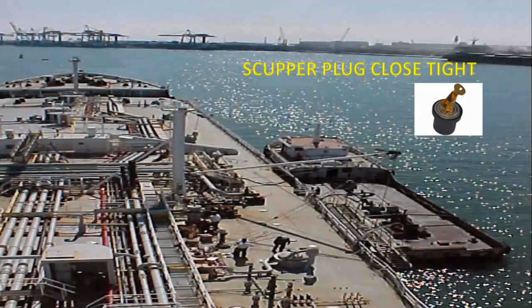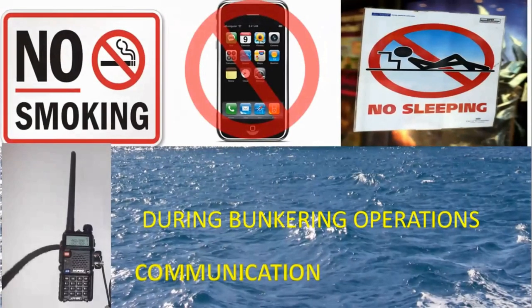During bunkering, it is engineering practice to put scupper plugs all over the vessel to avoid, in case of pollution, any leaking or fuel dropping into the ocean. It is also required to have no smoking, no naked lights, and no cell phones near the bunker station, and no sleeping during bunker operations. Communication between the deck department, the engine department, and the bunker supplier is very essential.